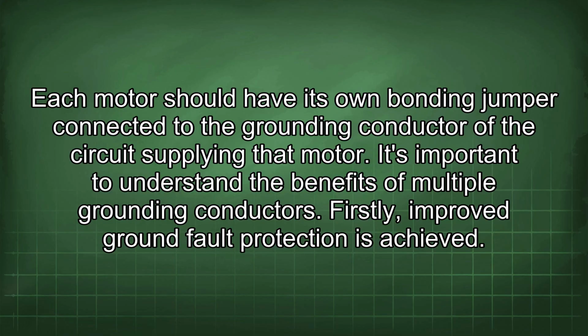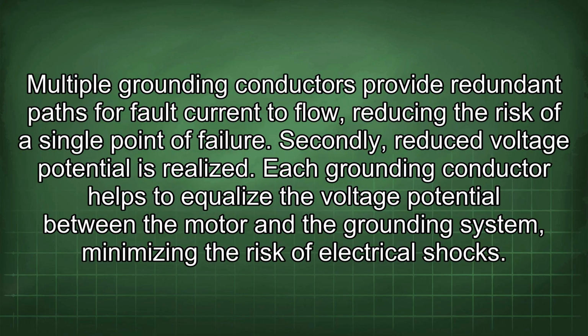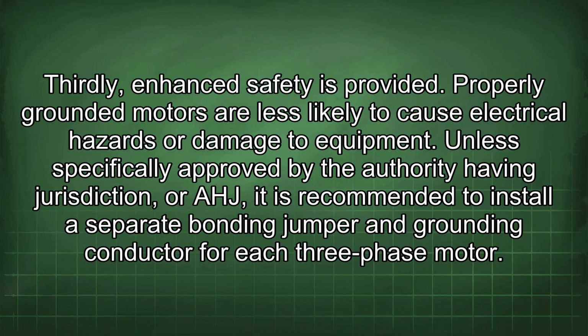It's important to understand the benefits of multiple grounding conductors. Firstly, improved ground fault protection is achieved. Multiple grounding conductors provide redundant paths for fault current to flow, reducing the risk of a single point of failure. Secondly, reduced voltage potential is realized. Each grounding conductor helps to equalize the voltage potential between the motor and the grounding system, minimizing the risk of electrical shocks. Thirdly, enhanced safety is provided. Properly grounded motors are less likely to cause electrical hazards or damage to equipment.